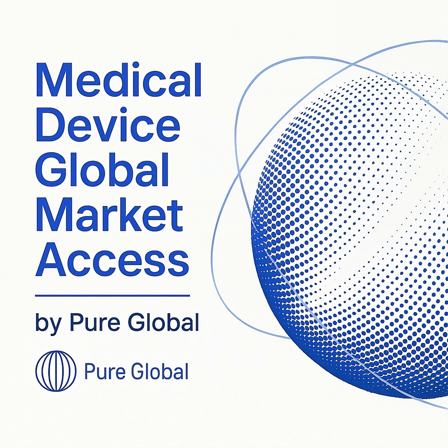So, how does this unlock global markets? While certification to ISO 13485 is not a direct legal requirement in every country, it is the globally recognized model for proving compliance. In the European Union, it is the harmonized standard used to demonstrate conformity with the quality management system requirements of the Medical Device Regulation, MDR. It is a mandatory requirement for medical device licensing in Canada.